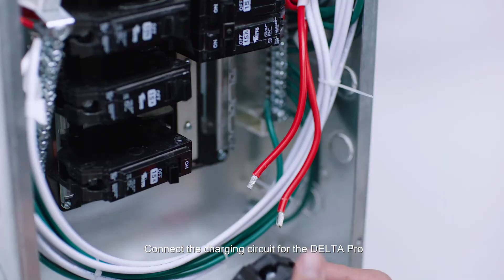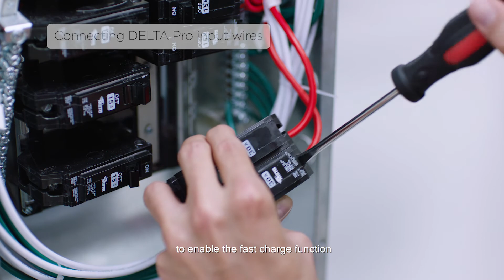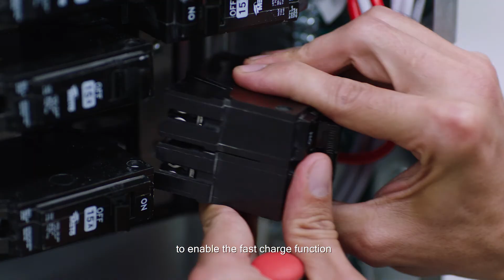Connect the charging circuit for the Delta Pro. Each Delta Pro needs to feed off one 30 ampere breaker from the main panel to enable the fast charge function. To connect the inputs, remove the hot wire from the circuit breaker. Connect each input wire to the corresponding circuit breaker.